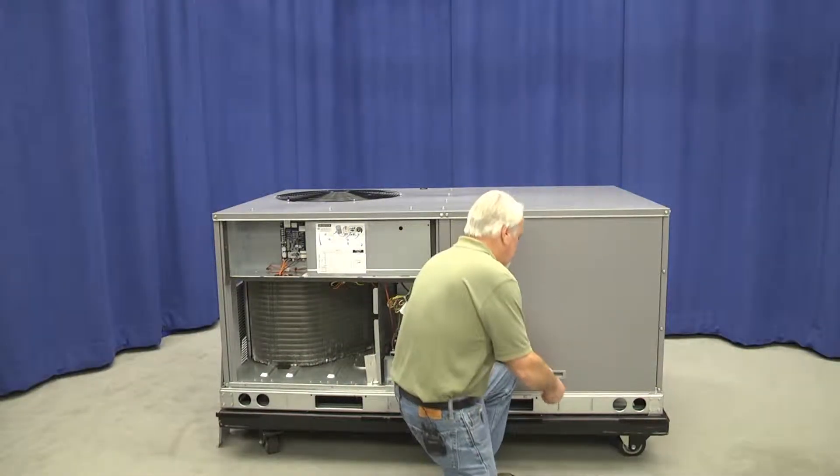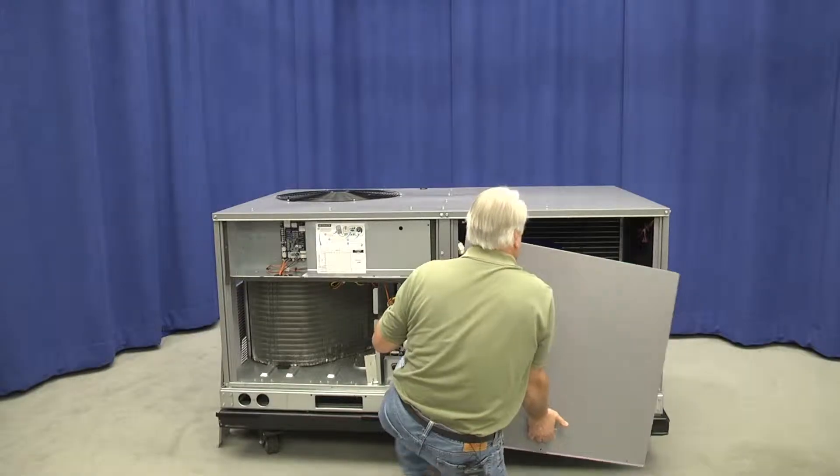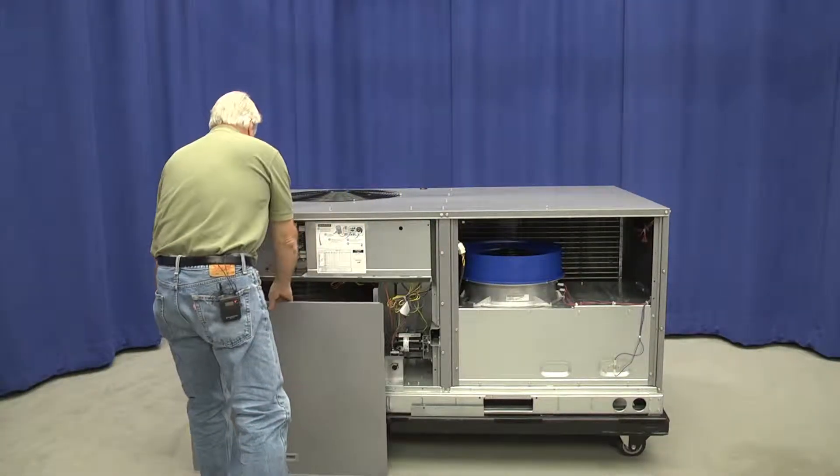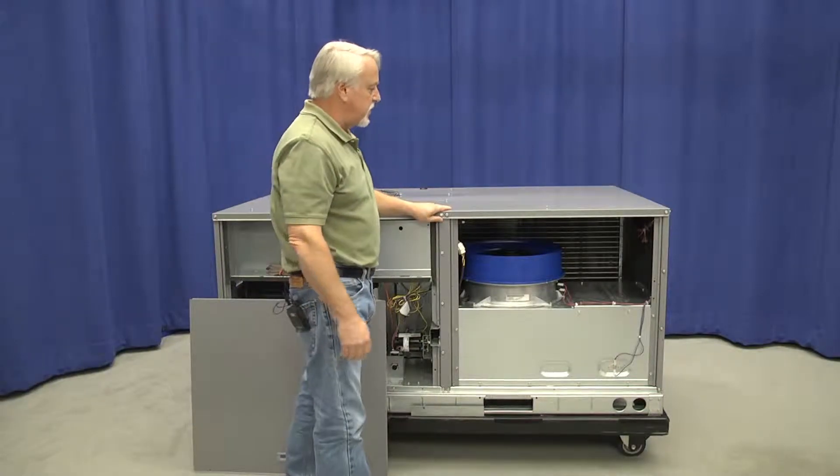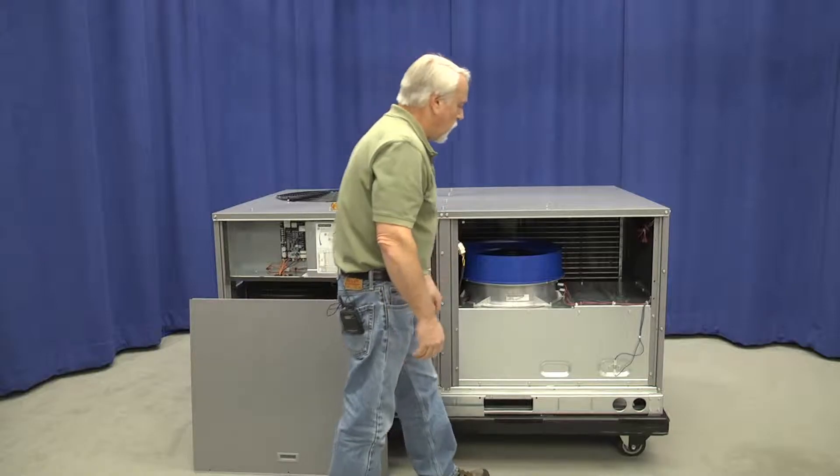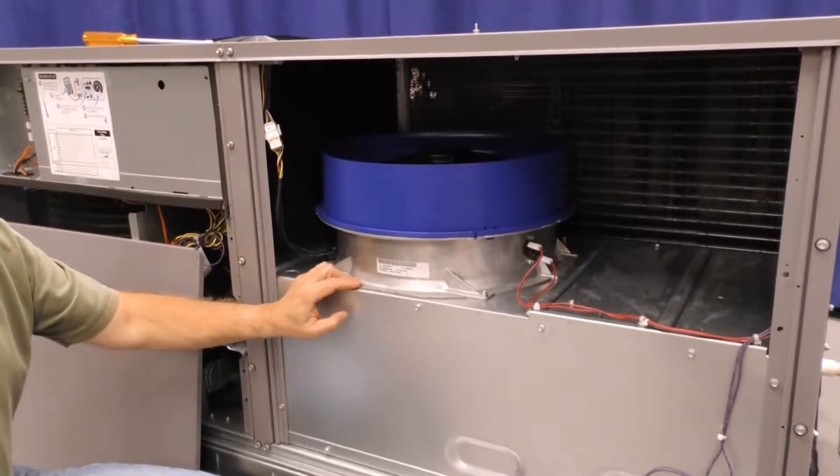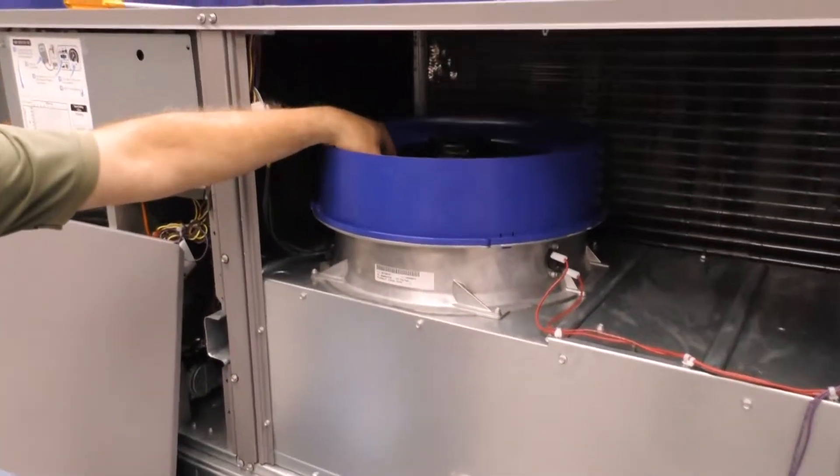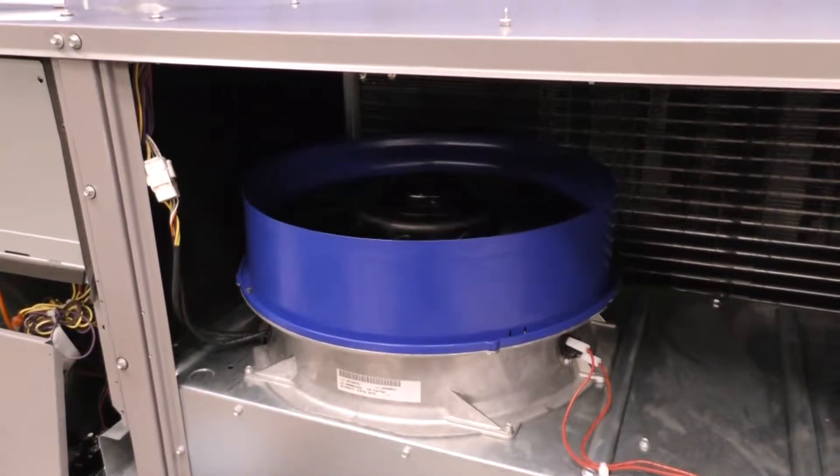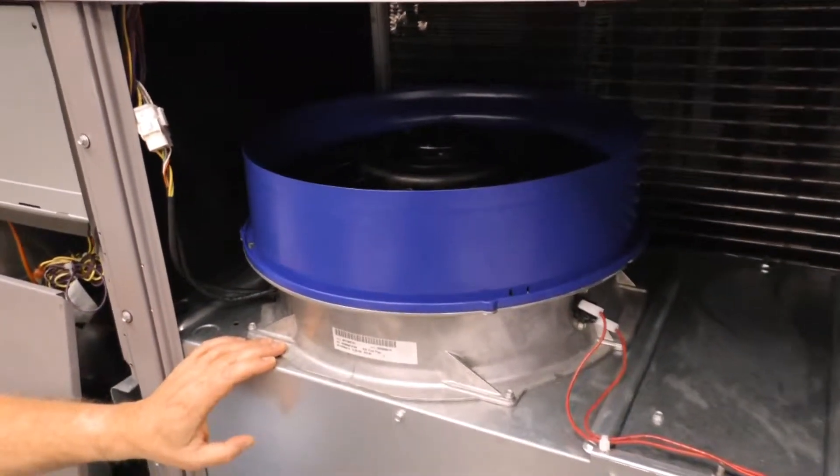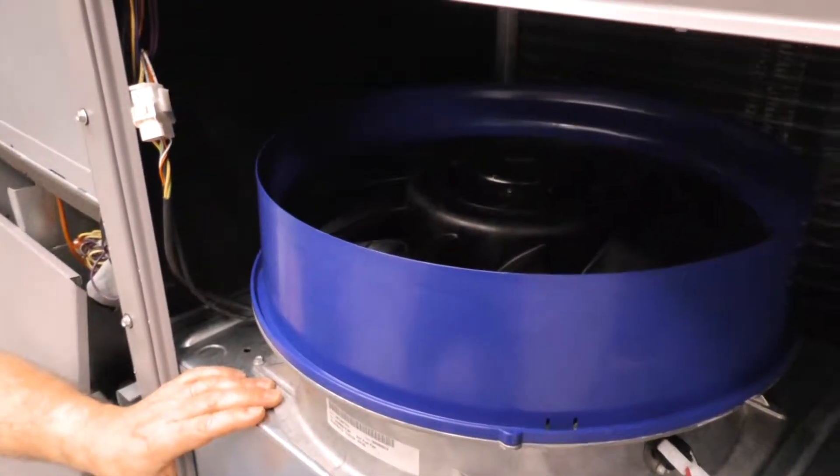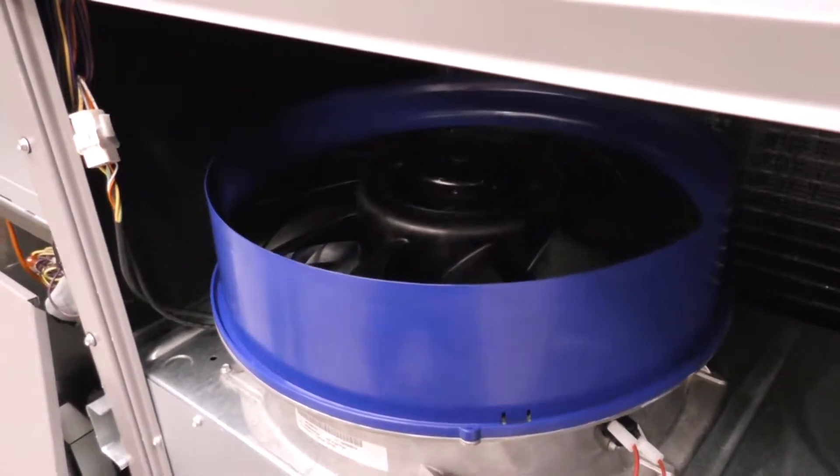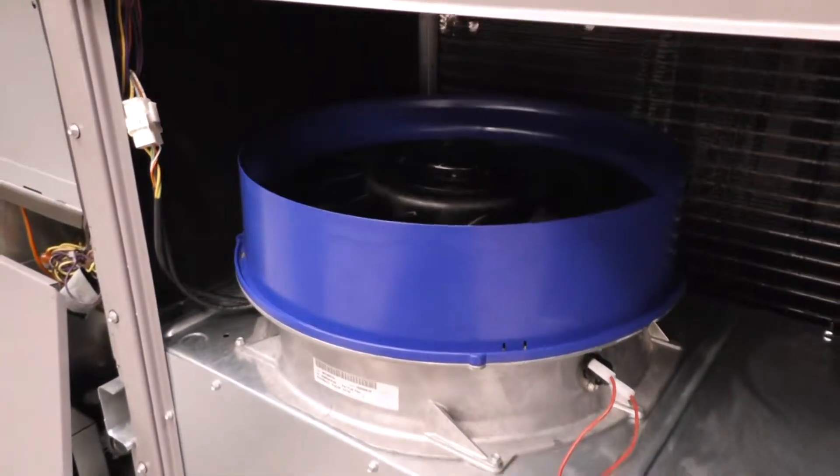Moving to the indoor fan panel, there is a significant difference compared to the old units or the current design. Previous to this, we had a forward curve fan. Now we are moving over to a vane axial fan. It's a composite fan, not a metal fan. It's direct drive. And it's controlled by an ECM motor. The use of this particular design with these ECM motors has eliminated the requirement for a variable frequency drive on some models.